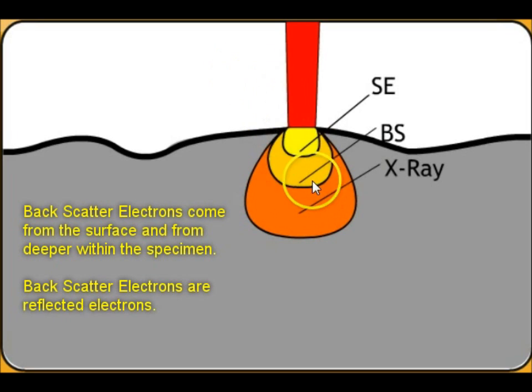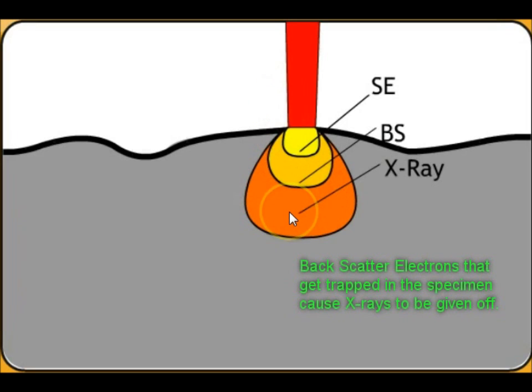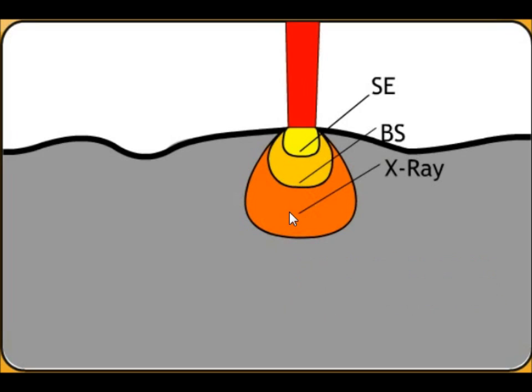The backscatter electrons are going to come from deeper in the specimen. So some will bounce right off the surface. Some will go deeper. And then the ones that are really deep actually never get back out again. So when they get absorbed, they give off x-rays. Now we actually don't have an x-ray detector for our scope. But you can do elemental analysis by using, by looking at x-rays. So the detectors that we have on our scope are the secondary electron detectors and the backscatter detectors.